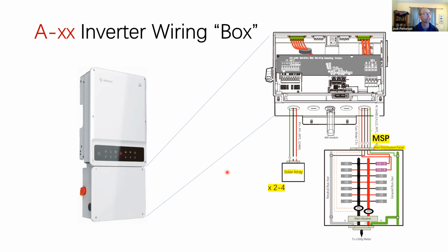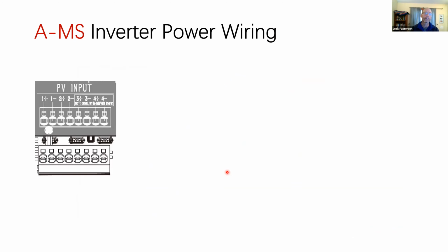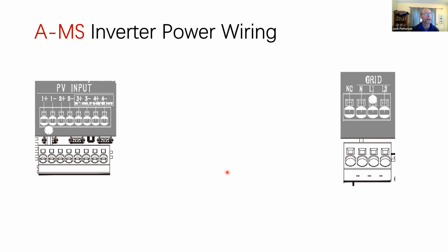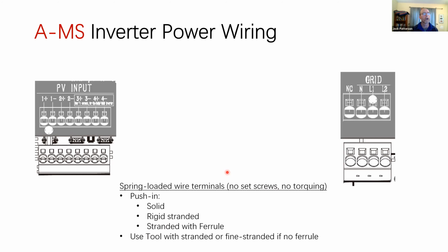In this illustration, we're showing what it would look like for wiring a PV inverter. Obviously, if you're doing a hybrid, there's a lot more connections, but I'm going to show both. So wiring the AMS, again, this is America only, medium single phase. Well, you can look at it as solar, but it really stands for single phase, because we do offer a 3-phase, right? We're going to introduce you to the C&I inverter at the end of this presentation. So as a PV inverter, we have PV inputs, and we have up to 4 MPPT. So that's why you see 4 sets of connections.